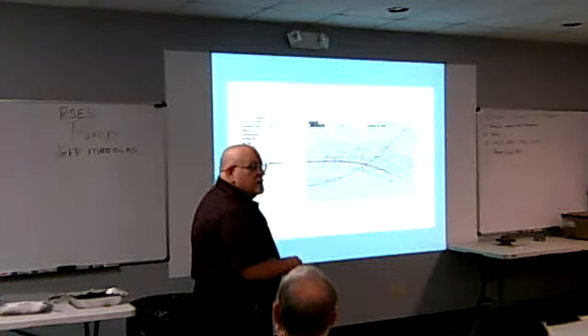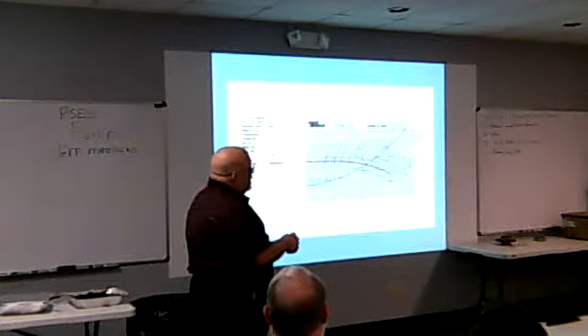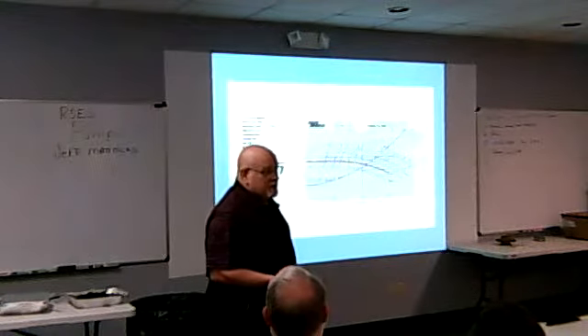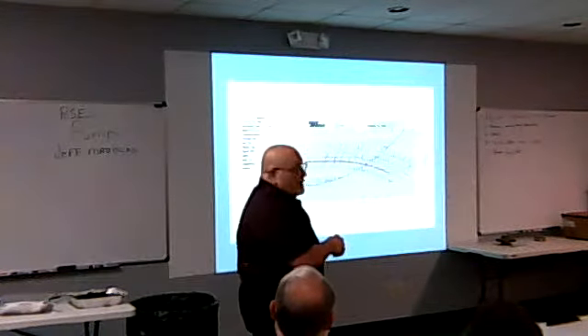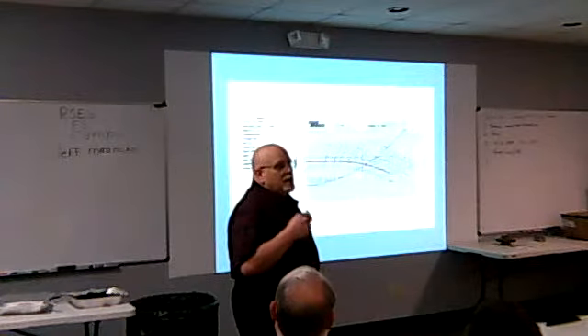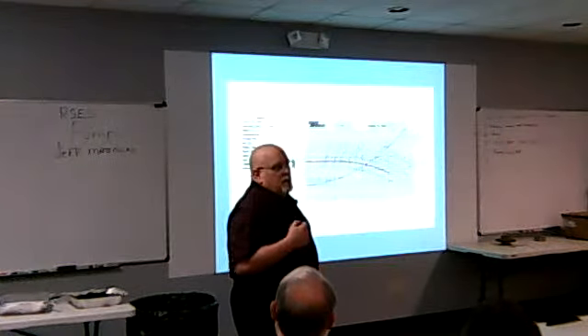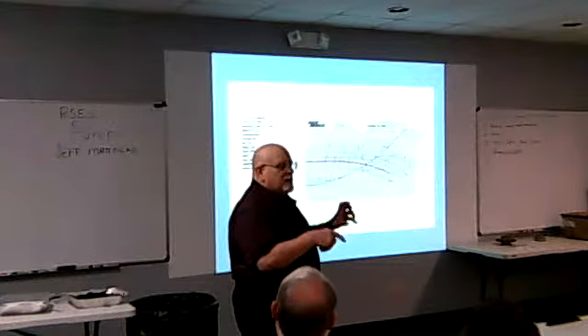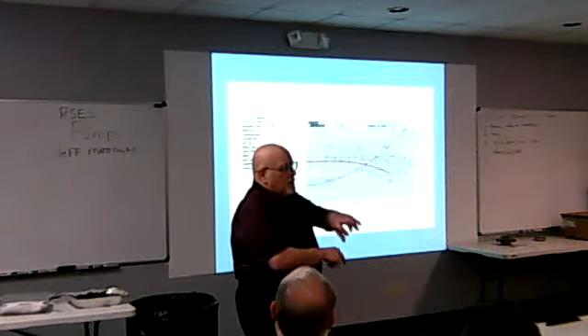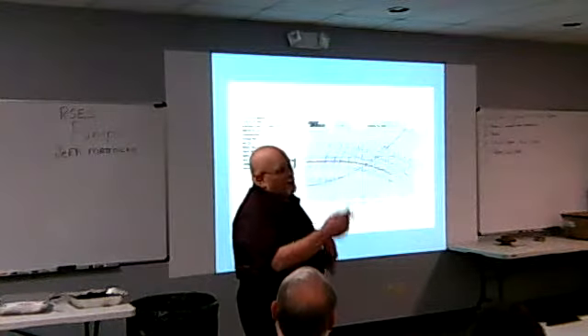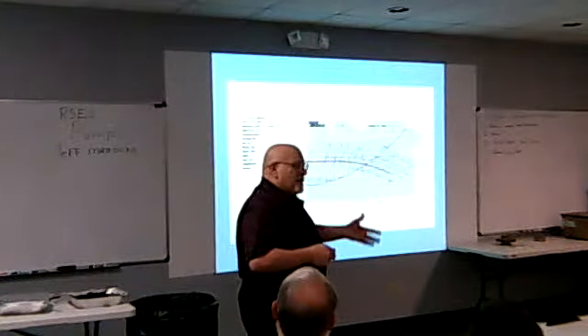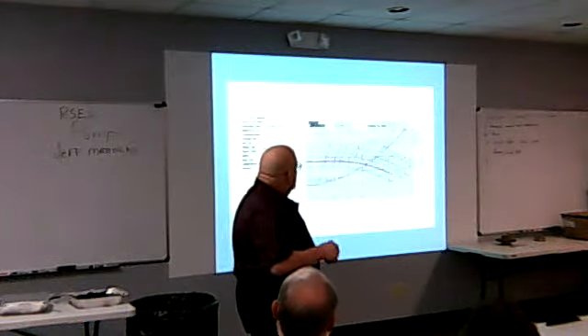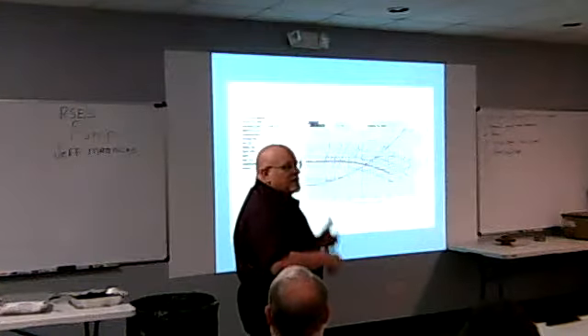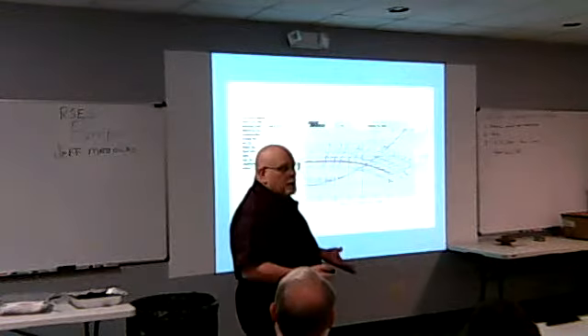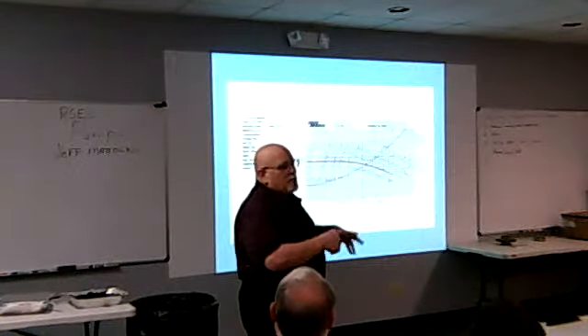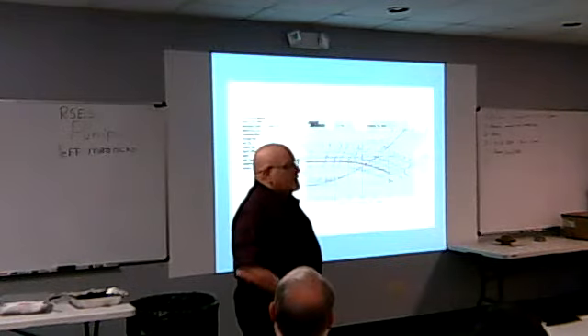Any questions on this so far? And each curve, every pump has an RPM. Typically for English or 60 cycle, you have 1160 RPM, 1750 RPM, 3600 RPM. 3600 is 2 poles in the motor, 1750 is 4, 1160 is 6 pole. When I go to 50 hertz, now you go to 1450, they're different RPM, but typically we use 60 hertz here. So 1160 slows it down and gives you less head, a quieter pump. At 3500, the impellers get smaller, but they're much noisier. Any questions?